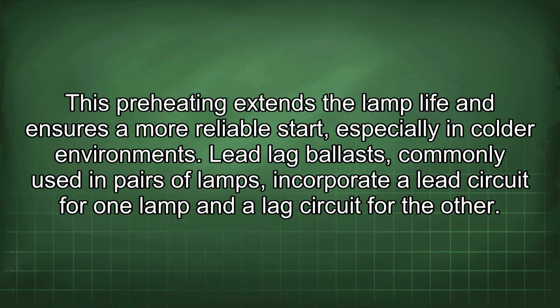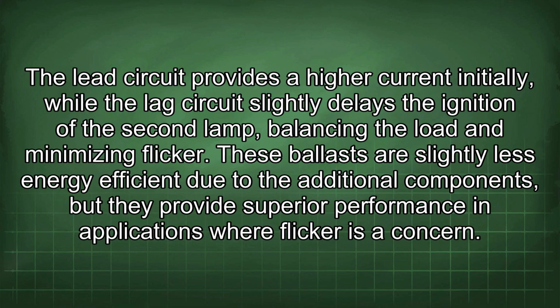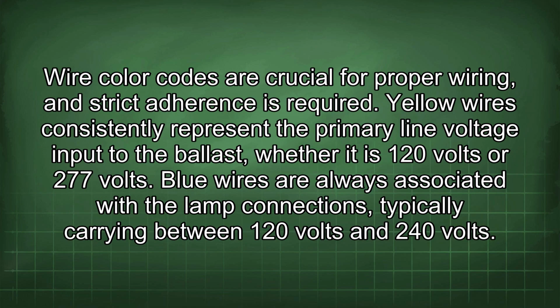Lead lag ballasts, commonly used in pairs of lamps, incorporate a lead circuit for one lamp and a lag circuit for the other. The lead circuit provides a higher current initially, while the lag circuit slightly delays the ignition of the second lamp, balancing the load and minimizing flicker. These ballasts are slightly less energy efficient due to the additional components, but they provide superior performance in applications where flicker is a concern. Wire color codes are crucial for proper wiring, and strict adherence is required.